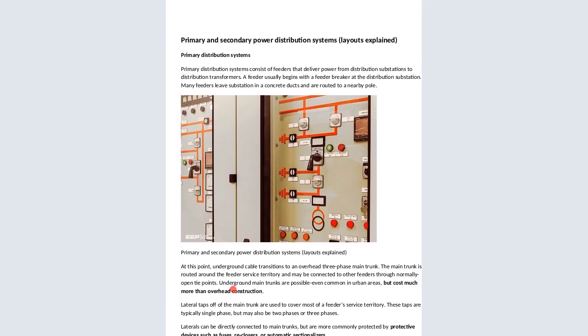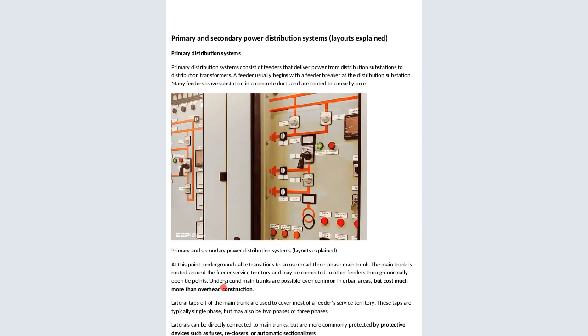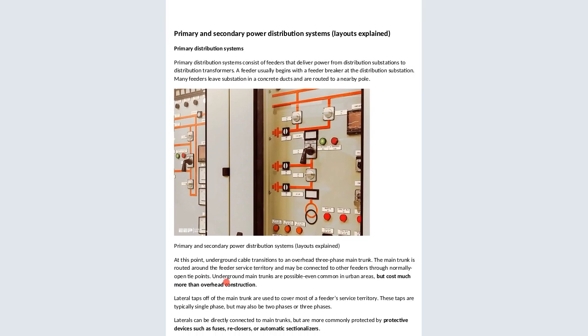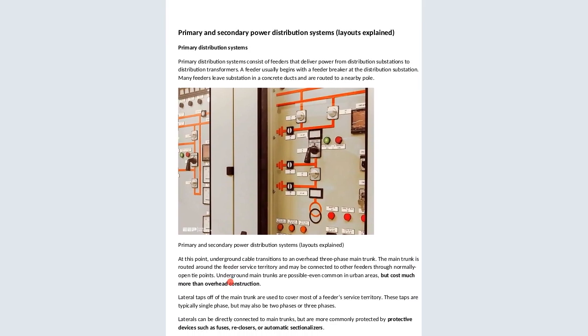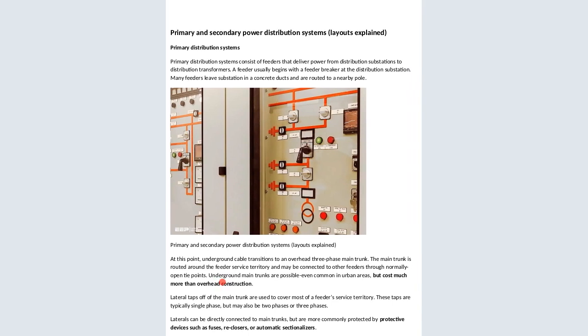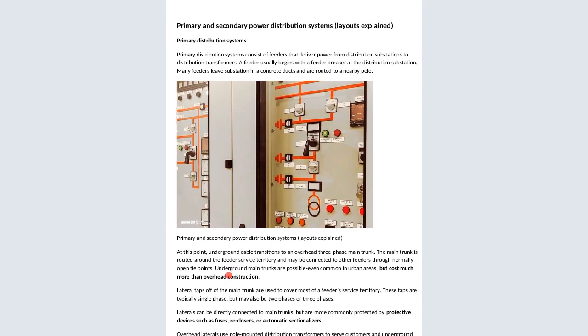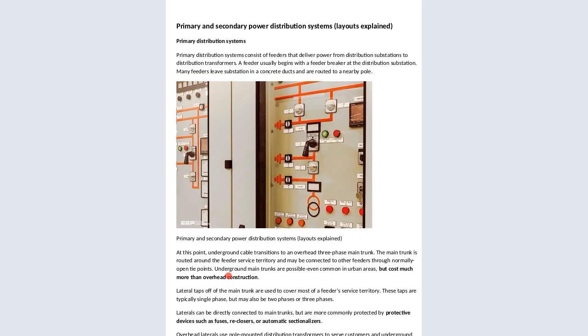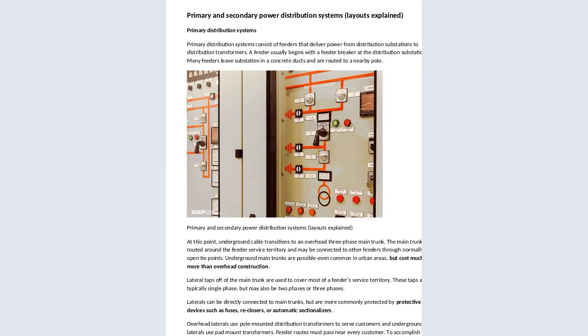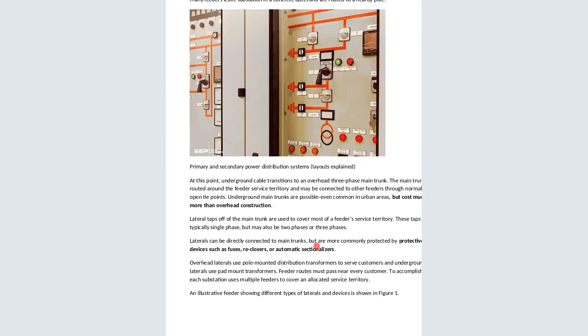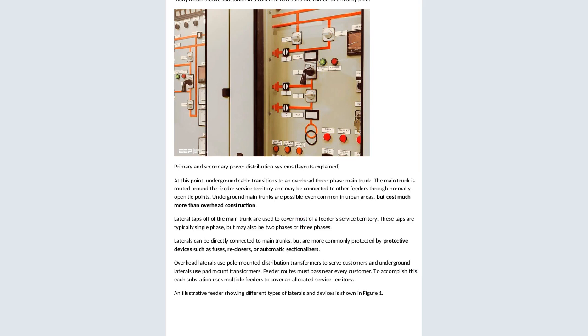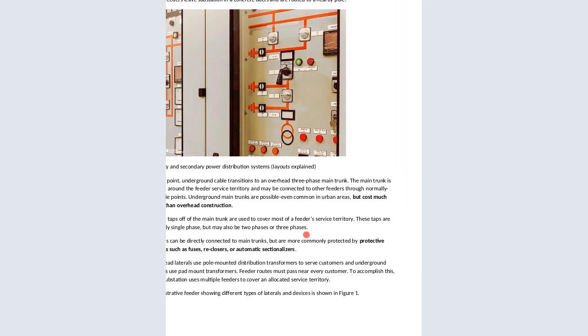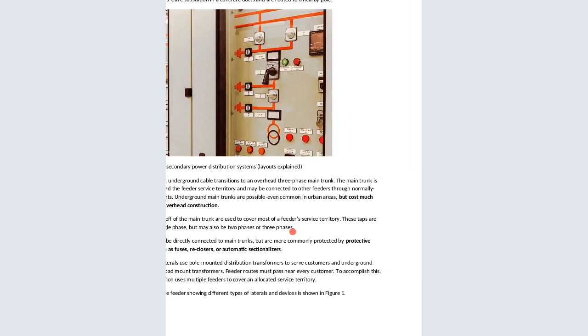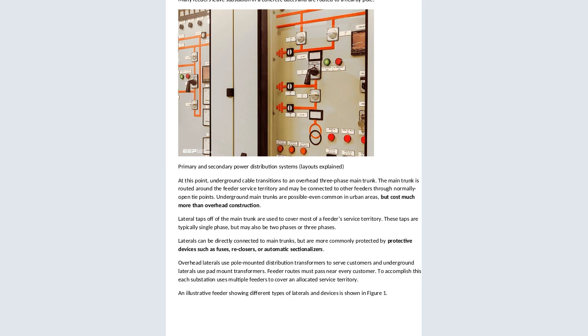Now we have the primary distribution system. The primary distribution system consists of feeders that deliver power from the distribution substation to distribution transformers. A feeder usually begins with a feeder breaker at the distribution substation. Many feeders leave the substation in a concrete duct and are routed to a nearby pole. You can now see the primary and secondary distribution system layouts explained. At this point, underground cables transition to an overhead three-phase main trunk. Remember, overhead lines are the ones that normally use poles, and underground are the ones that normally run below the ground.